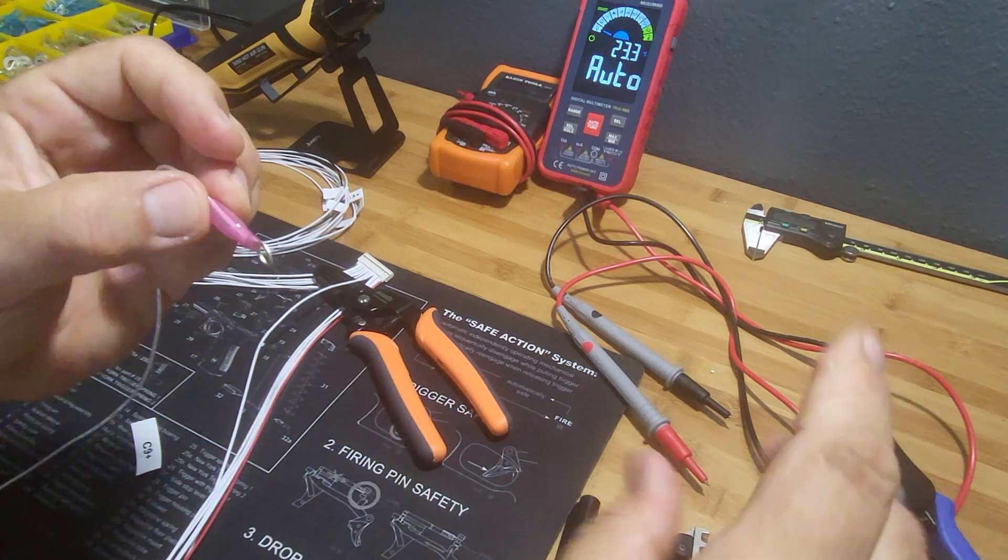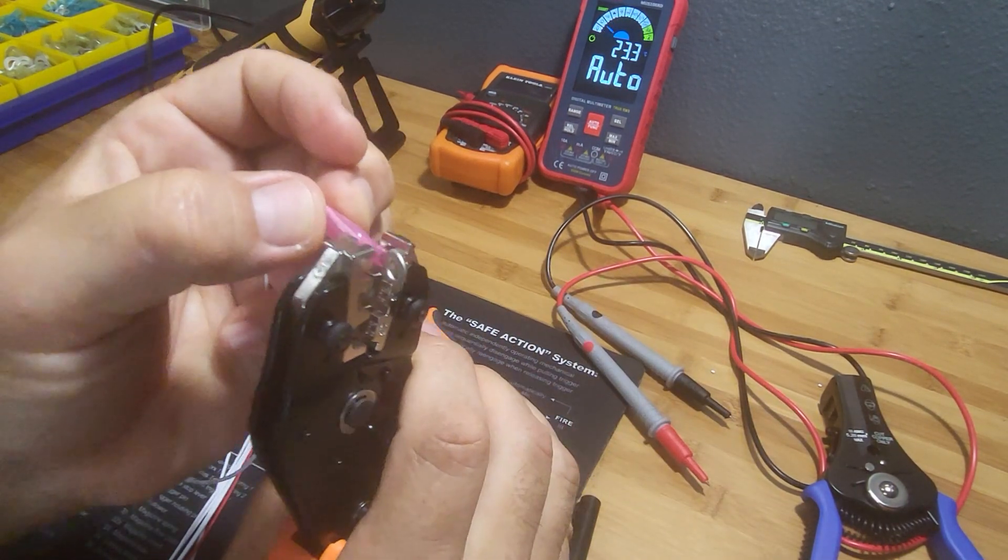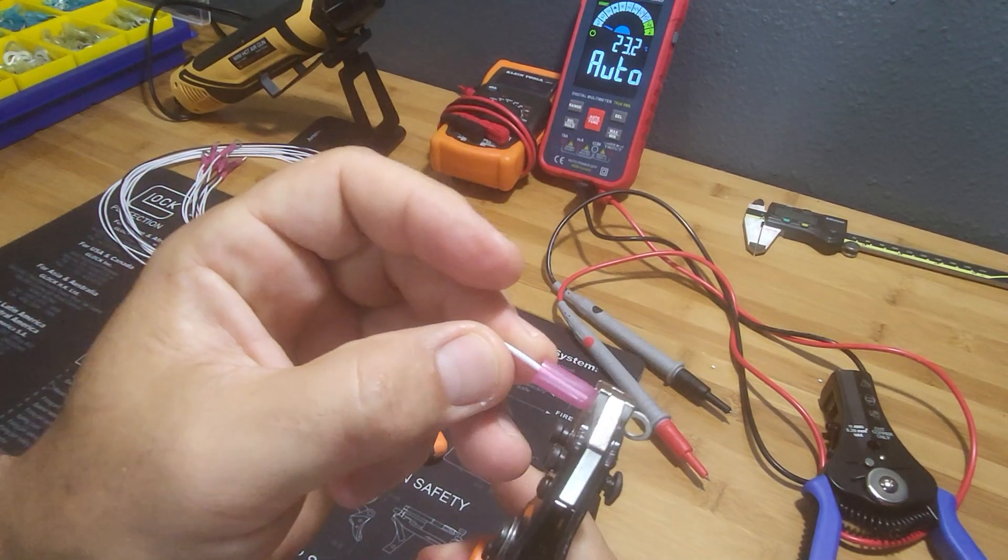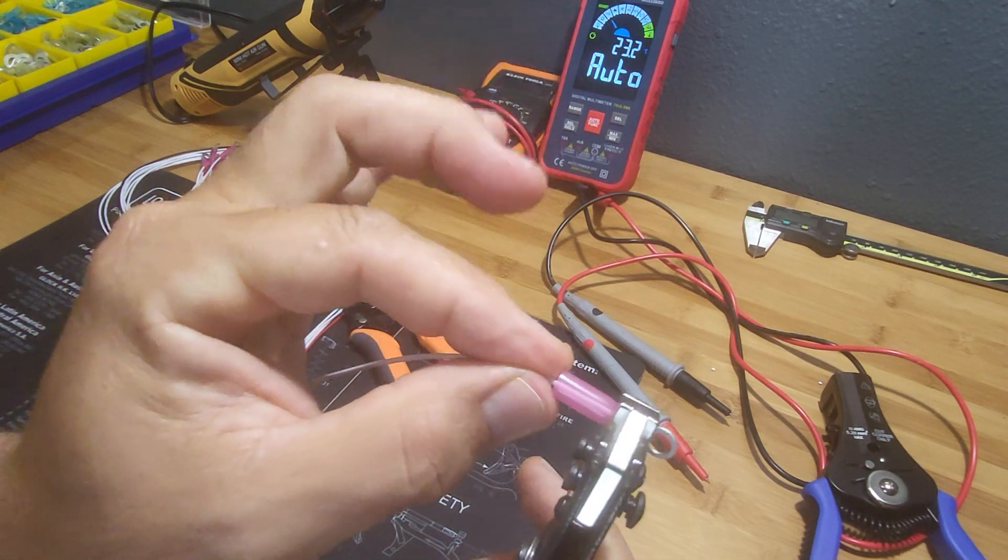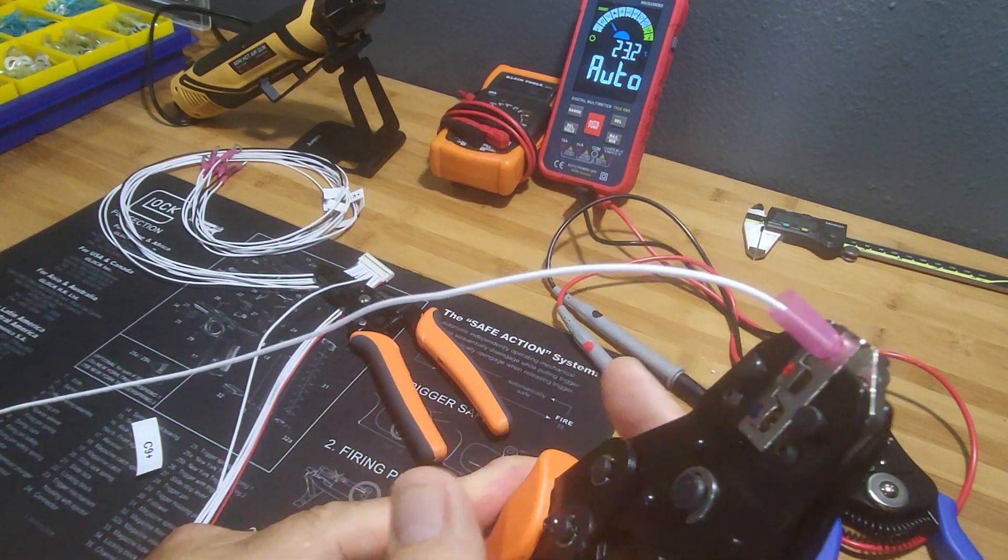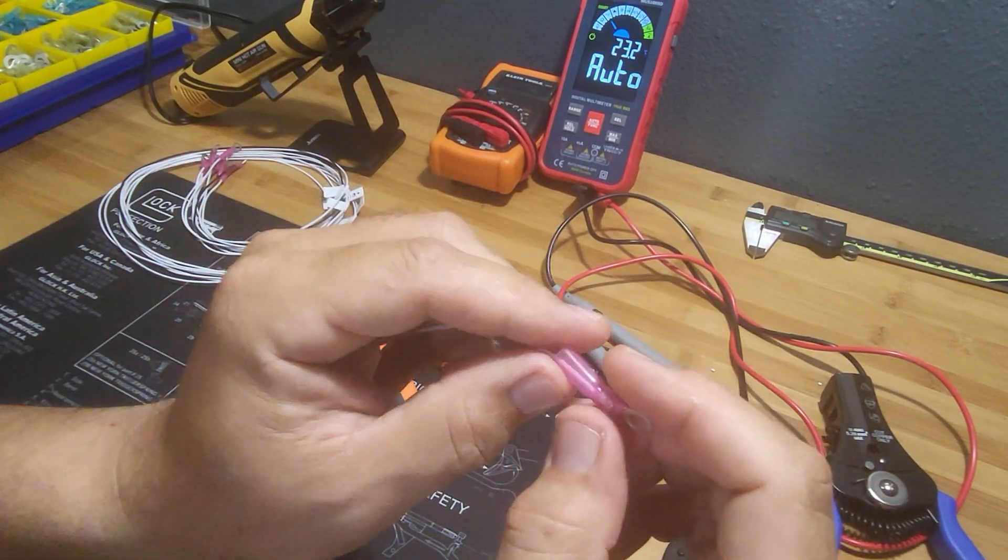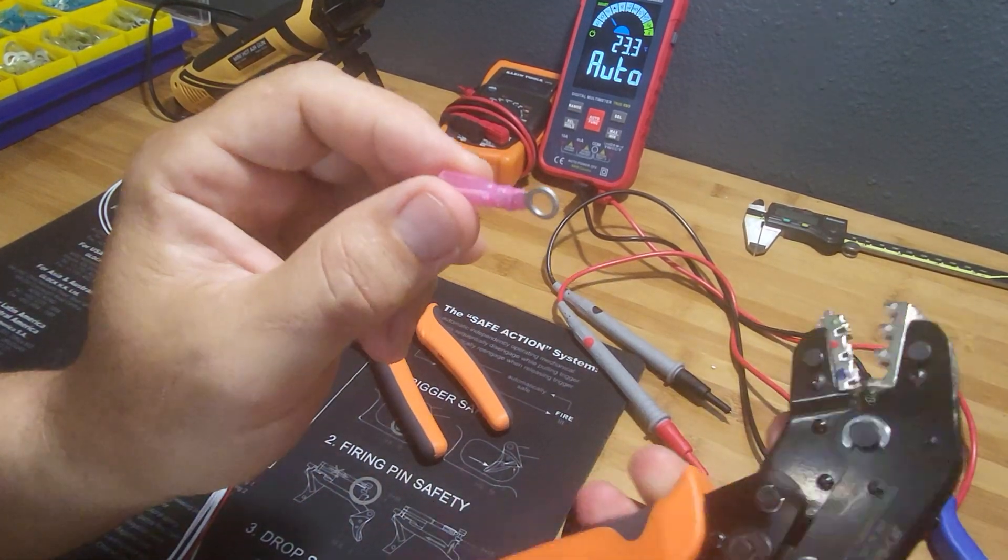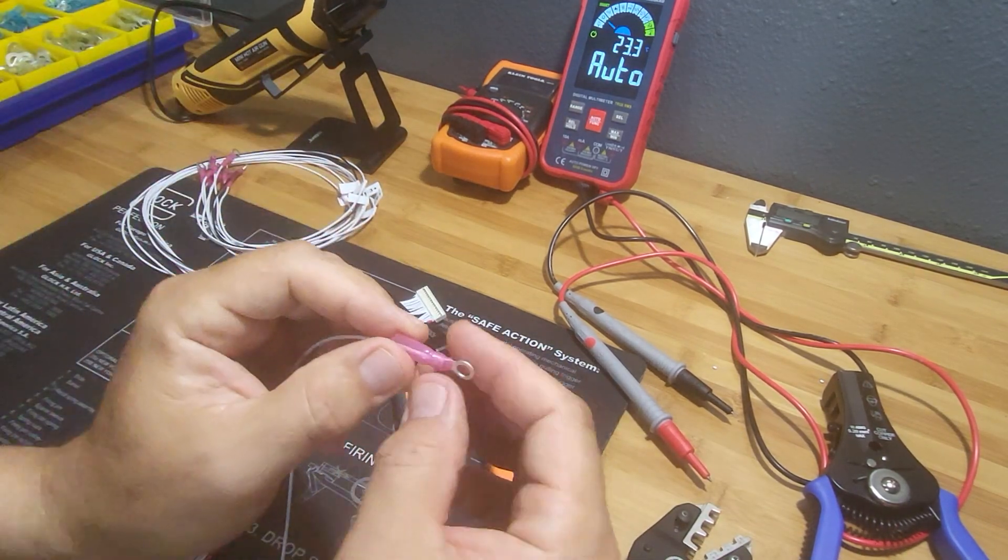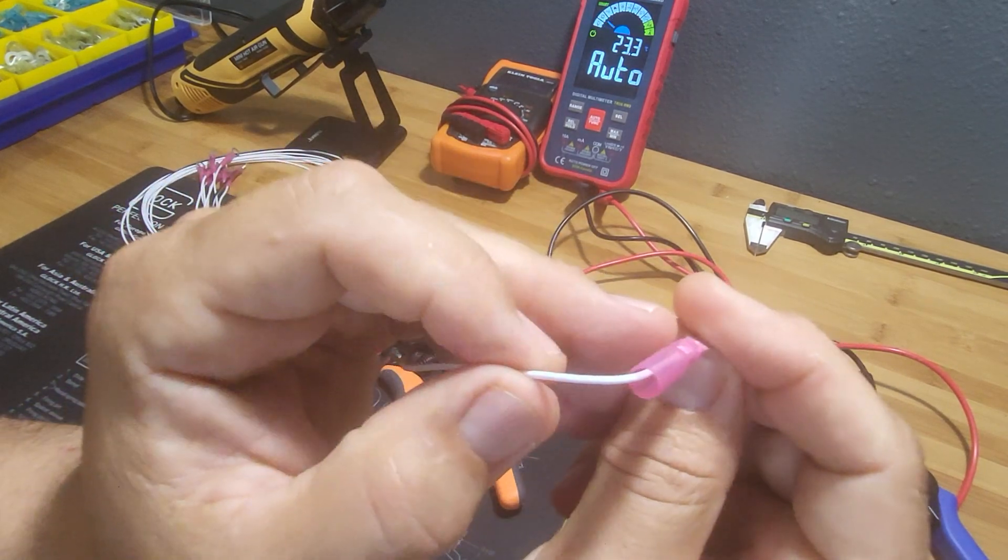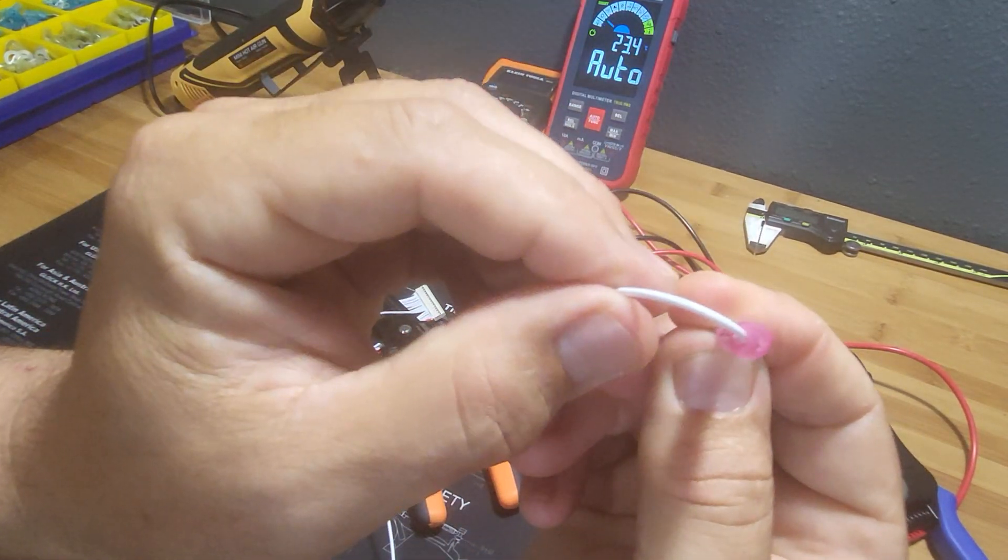Another problem I see people doing is when they set this crimp, they'll back this wire out a little bit accidentally and not get a good crimp. So make sure that's bottomed out in there, you have a good crimp on there, and make sure you set that crimp really well. You don't want to crimp too hard or you'll cut the wire off, so some crimpers are different than others. Just be aware of that when you're setting your crimps.